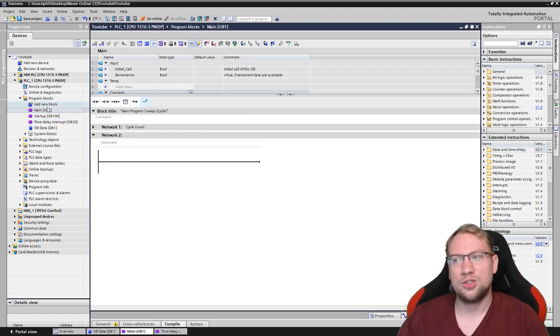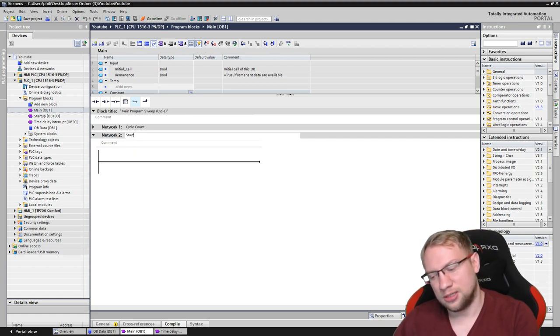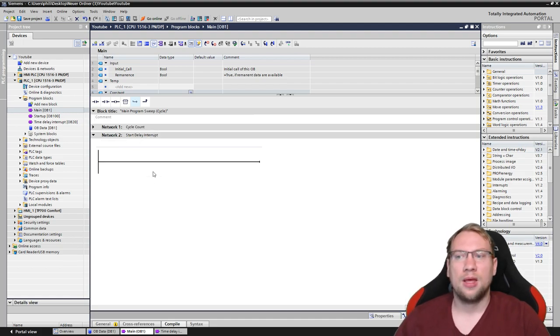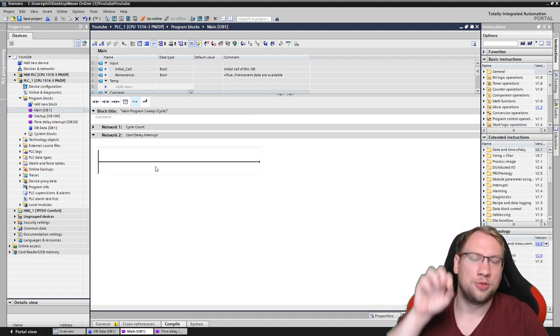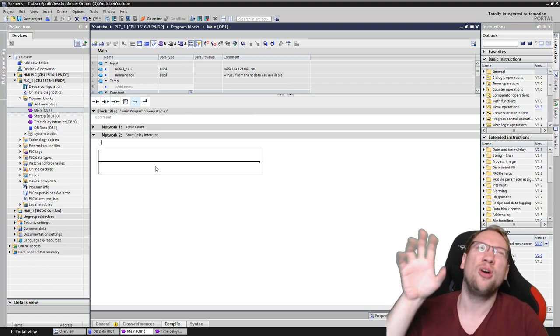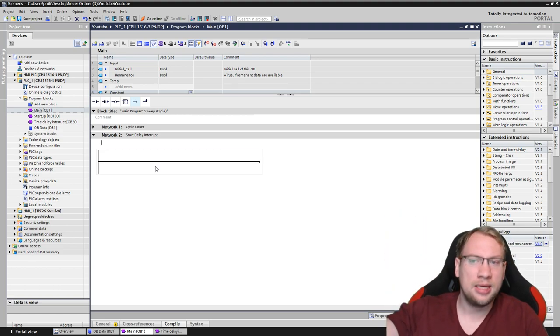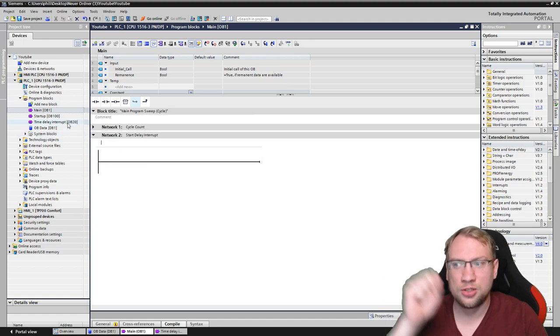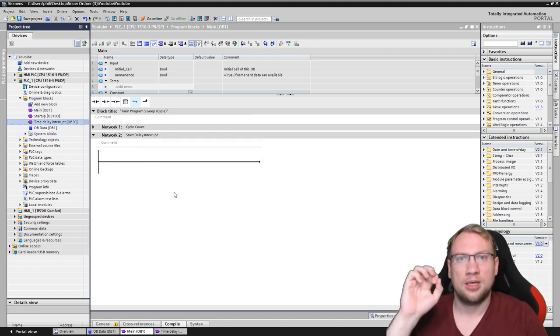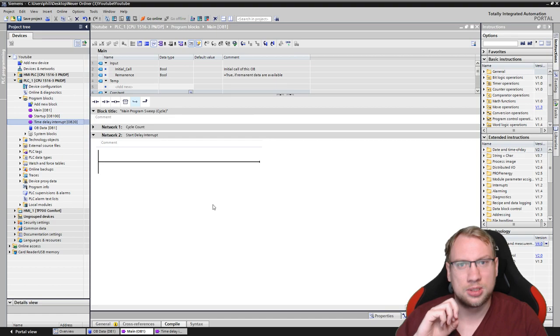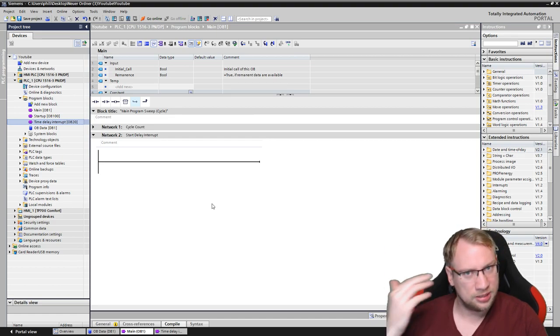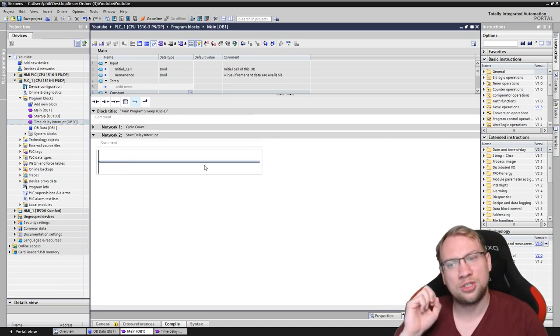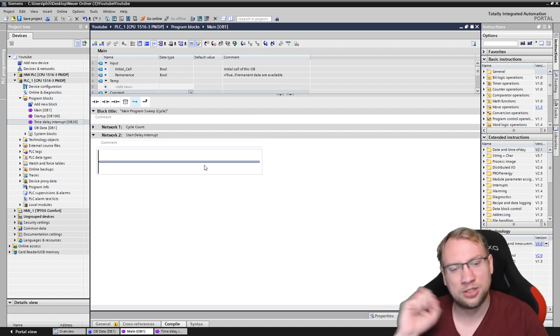So, in any other function, you can start a delay interrupt. And once you start the delay interrupt, you're telling the operating system, hey, operating system, please, in a specified amount of time, execute OB20, interrupting all the other blocks. This is a high priority. It's an interrupt. And we now just have to tell the operating system when to do it.